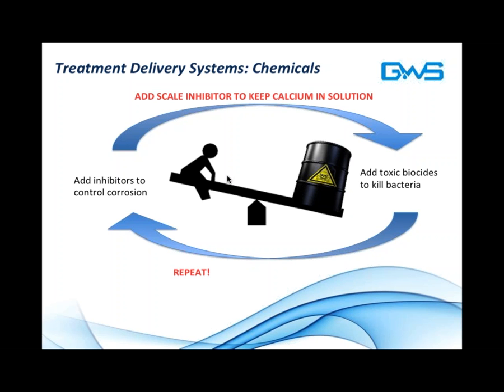Chemical inputs are continued and necessary every day, every month for the life of that tower, whether it's 5 years, 15 years, or 30 years. In addition, oftentimes biocides must be rotated because certain bugs become inoculated to the biocide that was originally added, and so now service partners are rotating biocides.